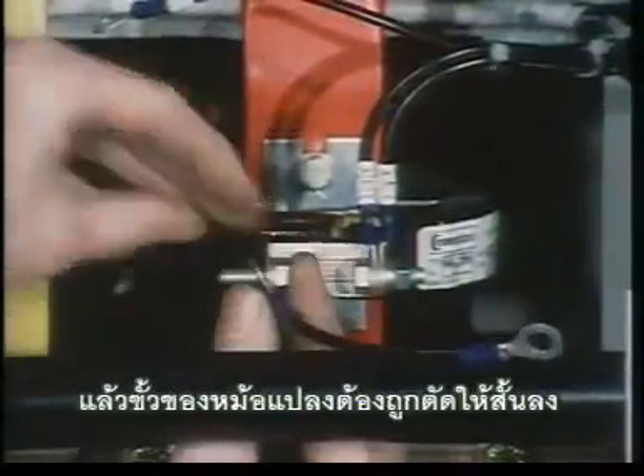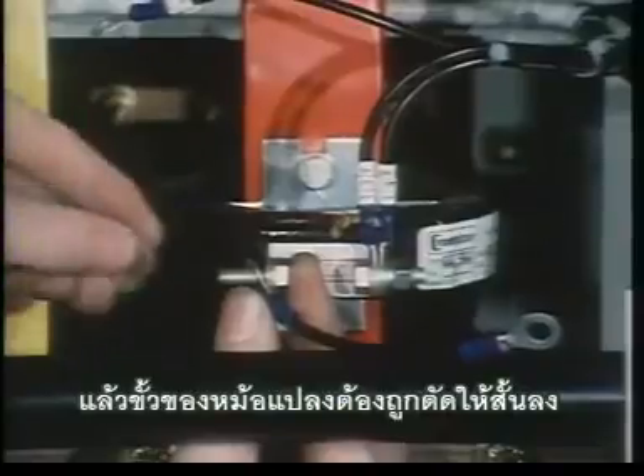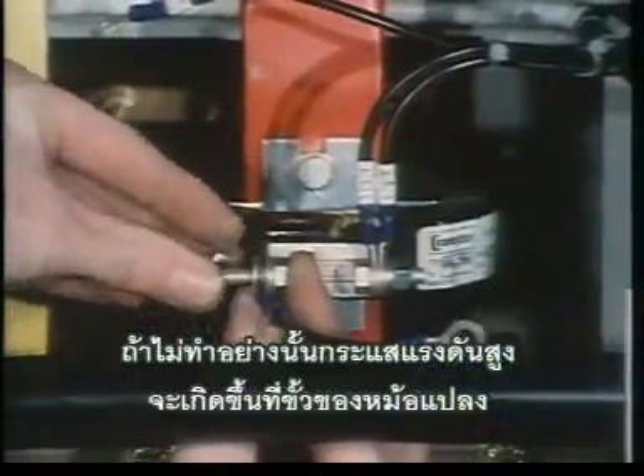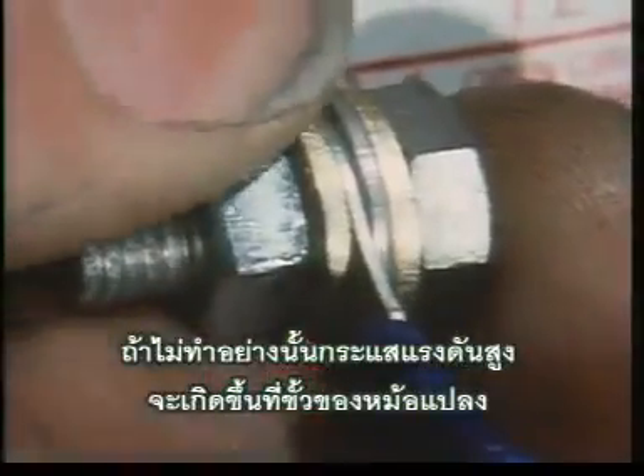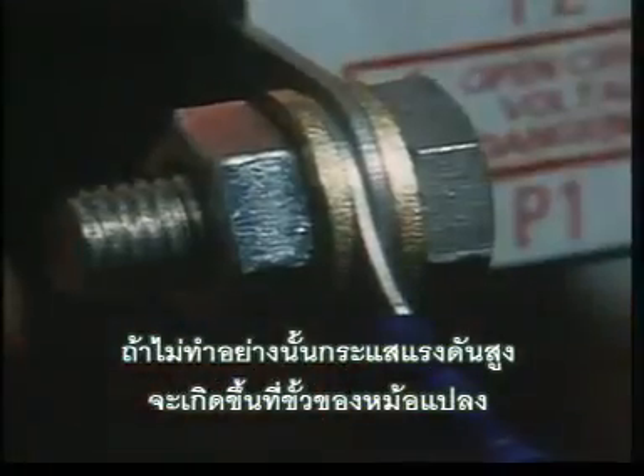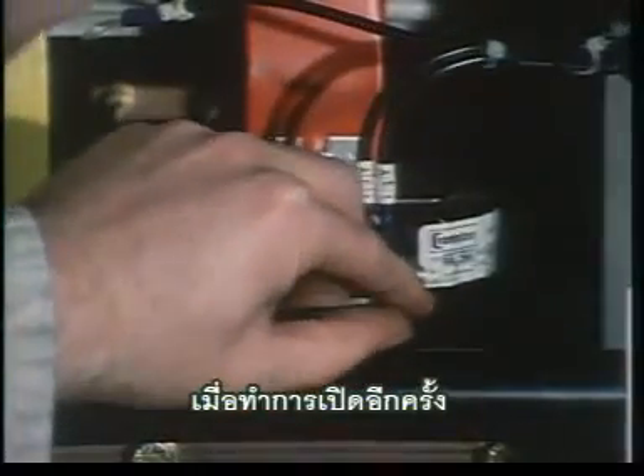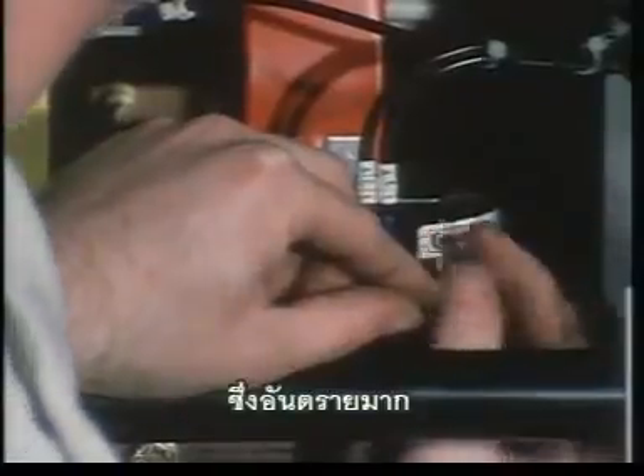Then the terminals of the current transformer must be shorted out. If this is not done, very high voltages will appear on the current transformer's terminals when the supply is switched on again. A most dangerous condition.